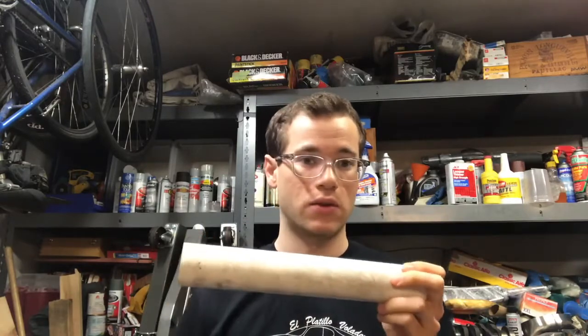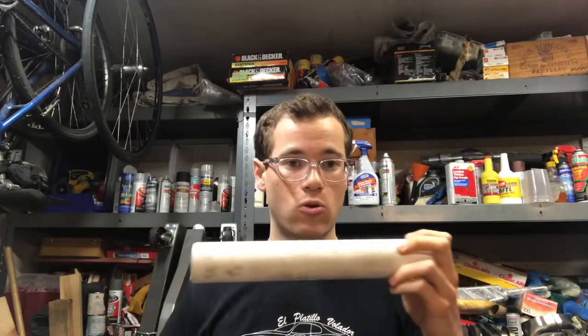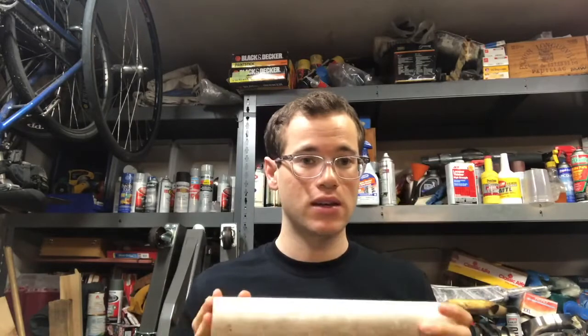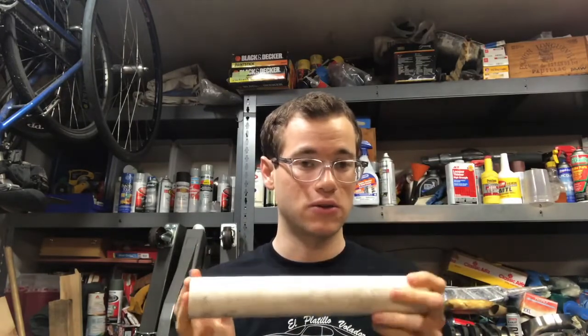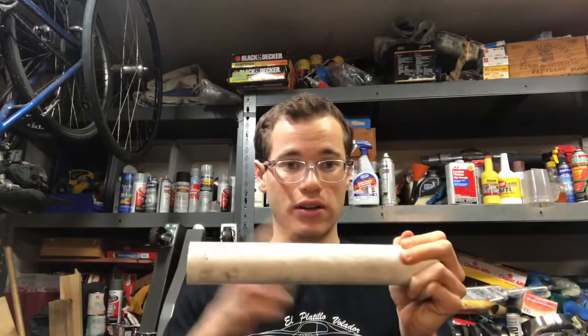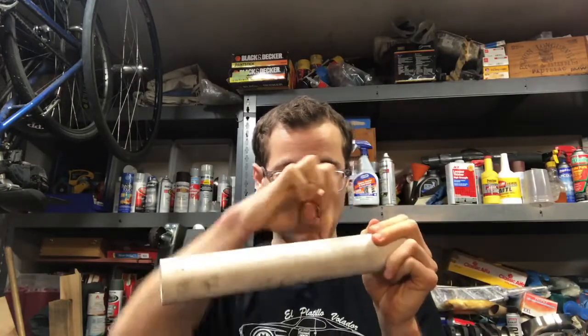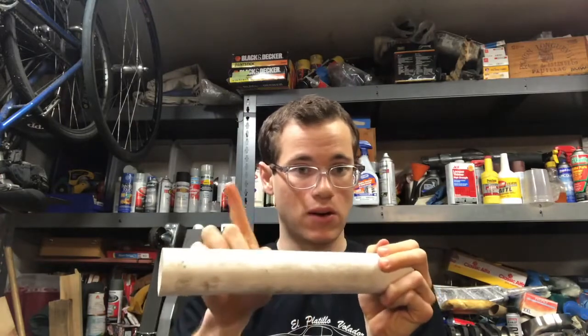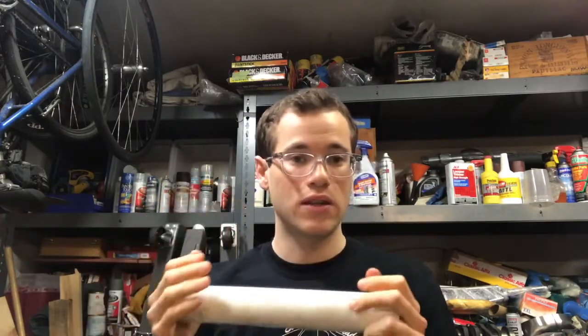Depending on the volumetric flow rate of the fluid moving through the pipe, the amount of time that ultrasonic signal takes to travel through the pipe will vary. This lets us draw correlations between the volumetric flow rate and how long it takes for a signal to travel from one point, bounce off the inner pipe diameter, and be reflected and received by a transmitter on the other side of the sensor. By charting this out, we can figure out the flow rates of fluids inside a pipe.